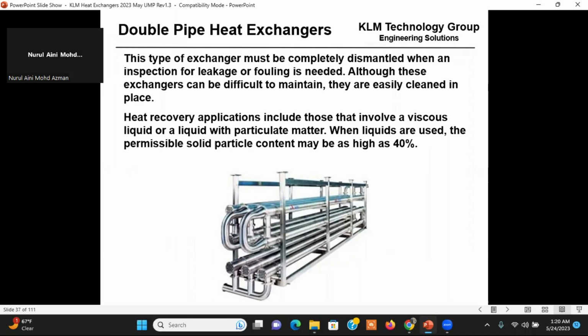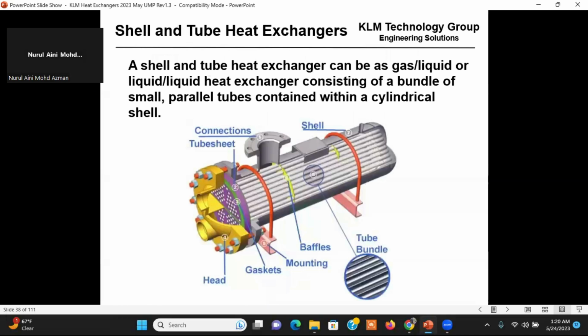Heat recovery applications include those with a very viscous liquid and a liquid with particulate matter. When liquids are used, the suspended solids can be as high as 40%. A shell and tube is really not designed for high solids, so you might use a double pipe heat exchanger.